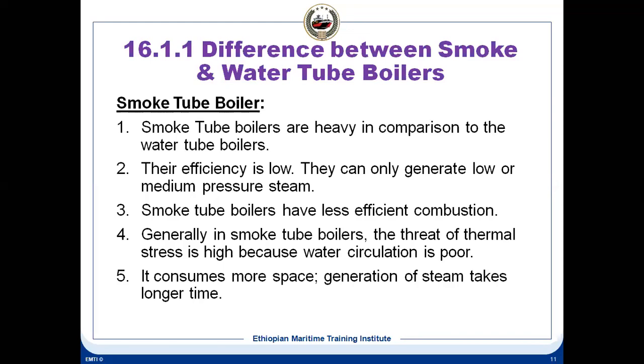it's quite dangerous. A smoke tube boiler, because it is bigger, consumes more space, and the generation of steam takes a much longer time. A smoke tube boiler, to warm it up from absolute cold, will take maybe anywhere between 8 to 12 hours, depending on the size of the boiler. And it consumes more space.